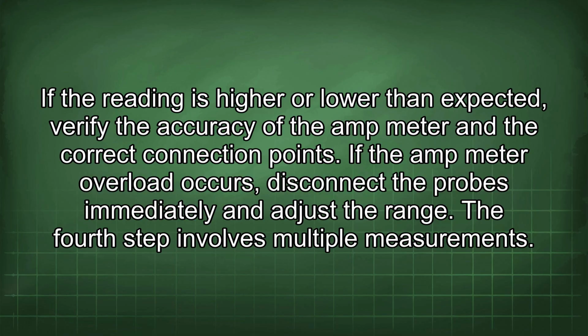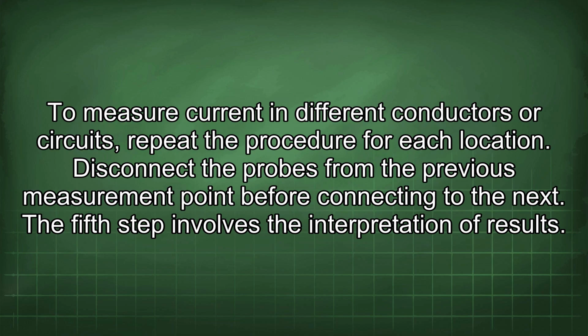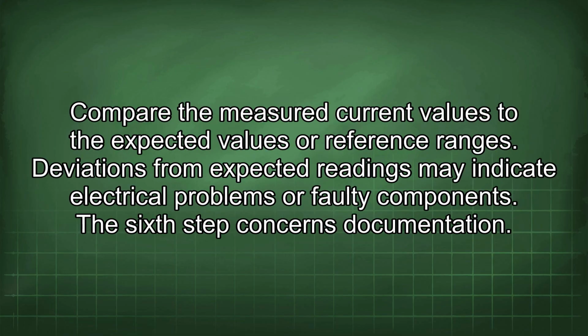The fourth step involves multiple measurements. To measure current in different conductors or circuits, repeat the procedure for each location. Disconnect the probes from the previous measurement point before connecting to the next. The fifth step involves the interpretation of results. Compare the measured current values to the expected values or reference ranges. Deviations from expected readings may indicate electrical problems or faulty components.